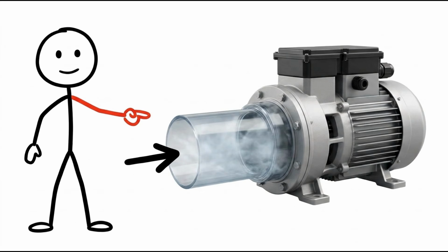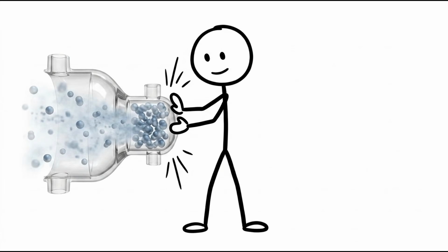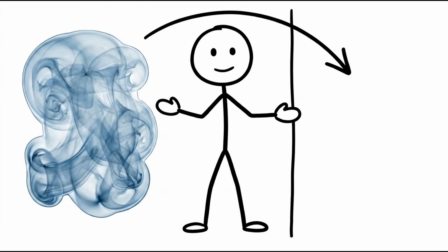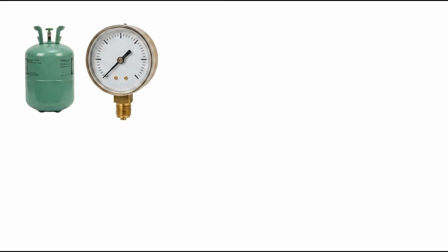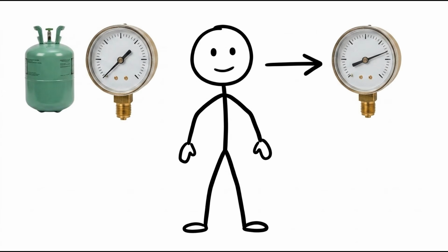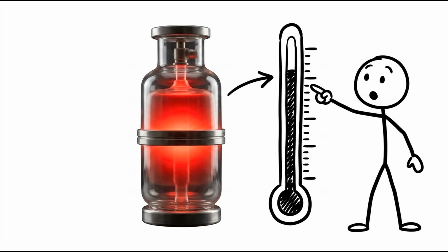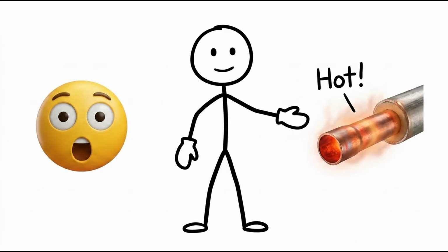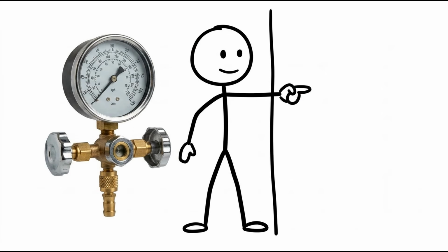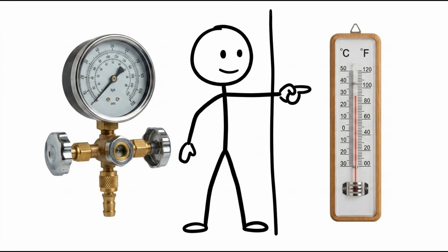As the gas is compressed, two important changes occur simultaneously. Its pressure increases dramatically, and its temperature rises well above the outdoor air temperature. This may seem surprising because many people expect an air conditioner to make everything colder. In reality, the refrigerant leaving the compressor is actually extremely hot. Making it hotter than the outside air is necessary, because heat can only leave the refrigerant if the refrigerant itself is warmer than its surroundings.